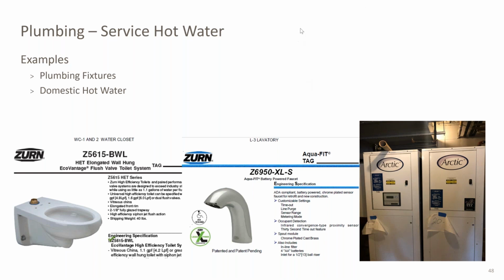In addition to that, we were able to do all low flow fixtures, including showers, sinks, faucets, anything that consumed hot water. So the first step was to reduce how much hot water we needed and how much we were consuming. And then the second step was to generate that hot water in the most efficient way possible, which was connecting that system to the geothermal system and taking heat out of that loop.